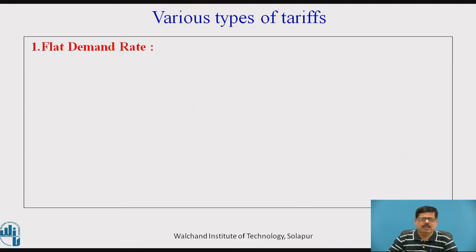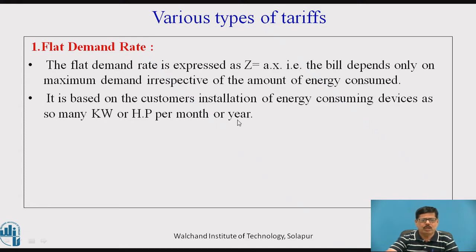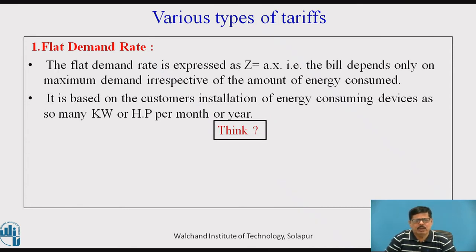The first and most simple form is the flat demand rate, expressed as Z = A × X. The bill depends only on the maximum demand X, irrespective of the amount of electrical energy consumed. It is based on the customer's installation of energy-consuming devices, such as so many kilowatt or HP per month or year. Consider for a moment which type of consumer this tariff is most suitable for.